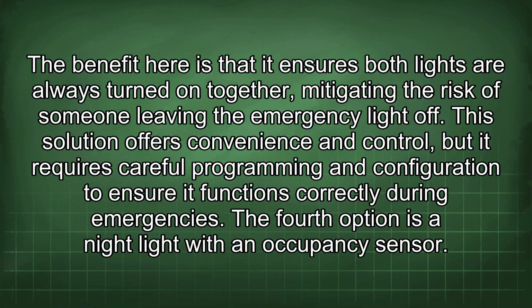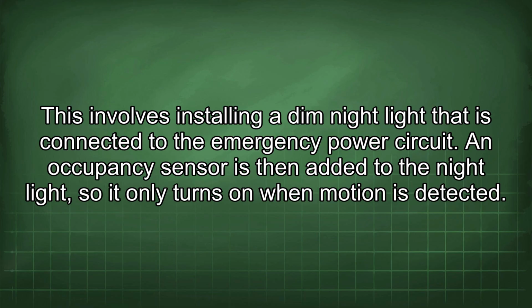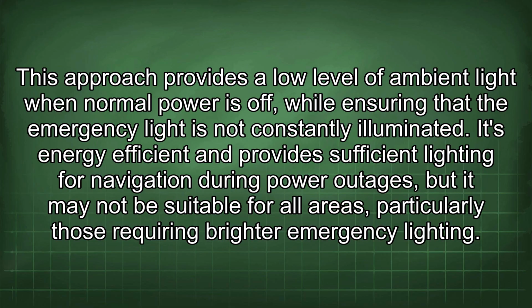The fourth option is a night light with an occupancy sensor. This involves installing a dim night light that is connected to the emergency power circuit. An occupancy sensor is then added to the night light, so it only turns on when motion is detected. This approach provides a low level of ambient light when normal power is off, while ensuring that the emergency light is not constantly illuminated. It's energy efficient and provides sufficient lighting for navigation during power outages, but it may not be suitable for all areas, particularly those requiring brighter emergency lighting.